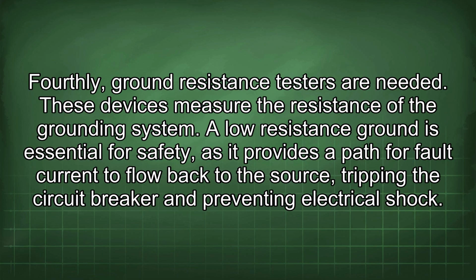Fourthly, ground resistance testers are needed. These devices measure the resistance of the grounding system. A low resistance ground is essential for safety, as it provides a path for fault current to flow back to the source, tripping the circuit breaker and preventing electrical shock.